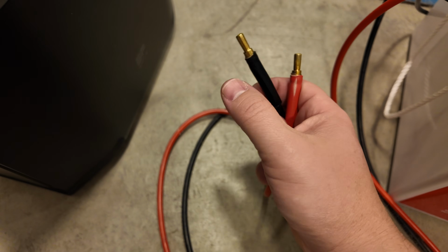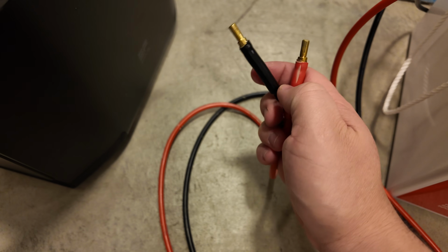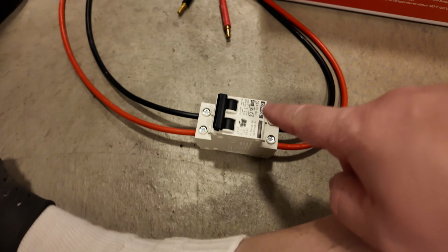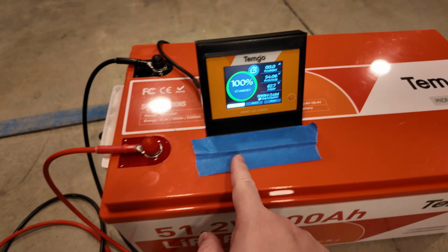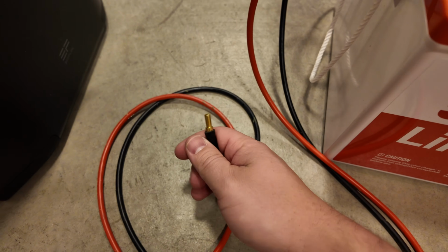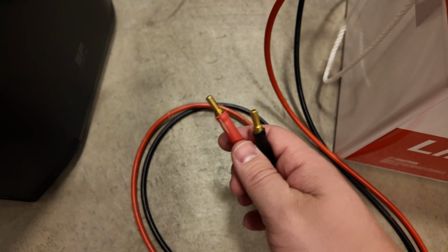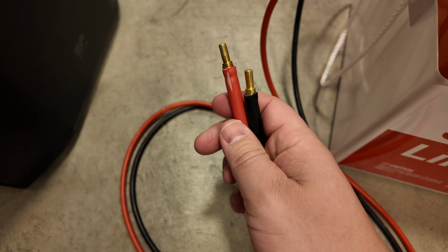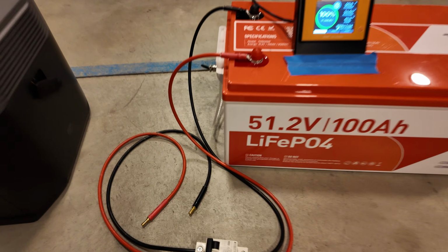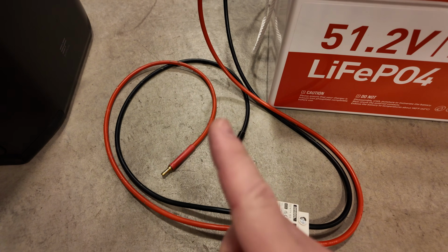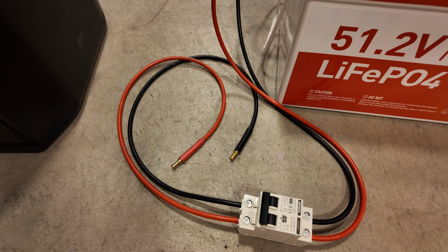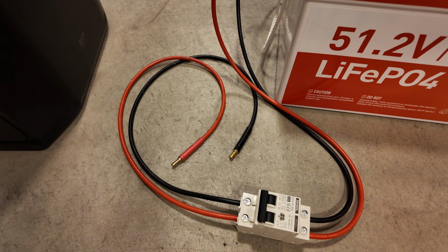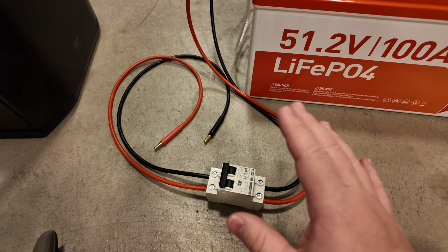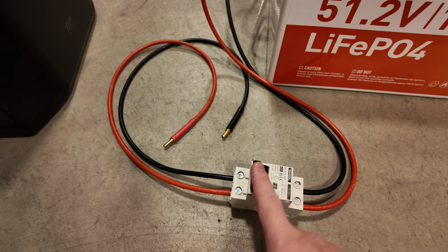You see how we've got two male ends fully exposed right here? I'm going to exercise caution even though my breaker is off and I've turned off the discharge on this battery, but still, what you definitely do not want to have happen is have this battery still on, have this still on, you go unplug this and these two somehow touch. That's going to be a dead short, and hopefully something trips, like this breaker or the BMS in the battery. But before any of that happens, there is going to be one heck of a spark and molten metal flying in different directions and all kinds of crazy bad stuff. So keep your head screwed on and ensure at all costs that this is turned off.